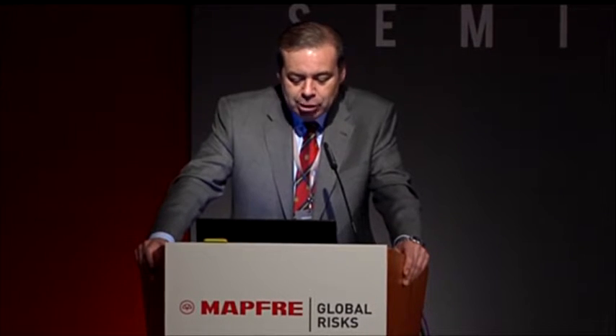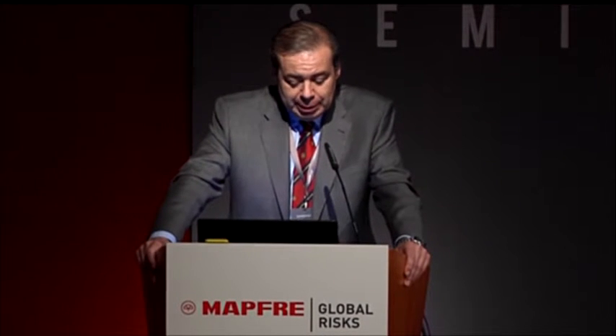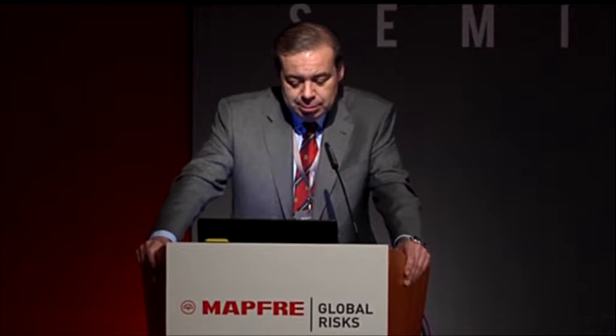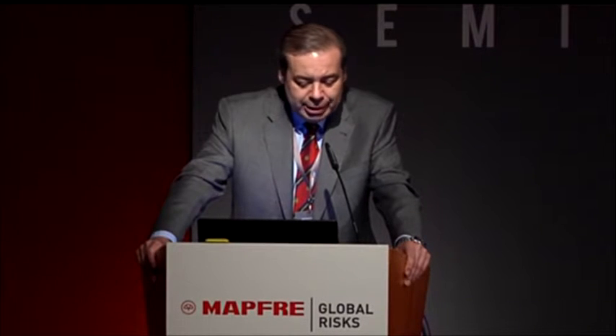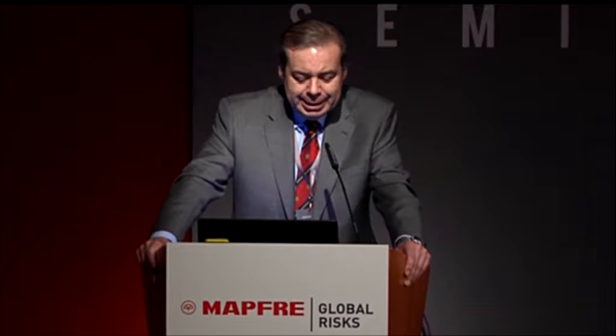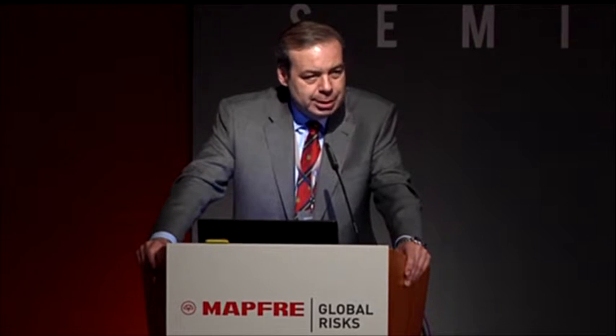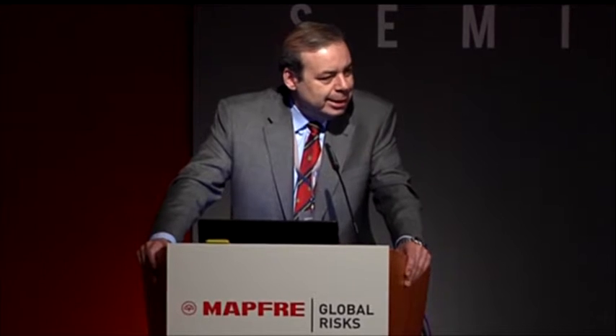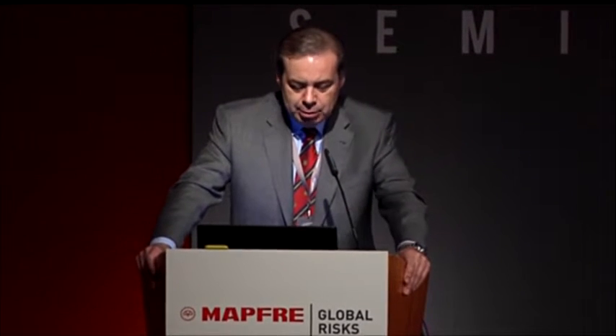As for the main failures in steam turbines, most of these failures have to do with the control and regulation elements. This is very logical as well. It's true that the system is much less rigid than in gas turbines. It is easier to make an operations mistake. In the gas turbines that are started up with sequencers, there are many backups and redundancies and safeguard mechanisms that are in place. So it's hard to make a human error in the case of gas turbines. In the case of steam turbines, the supervision during startup is done not by an automated system but by operations staff.